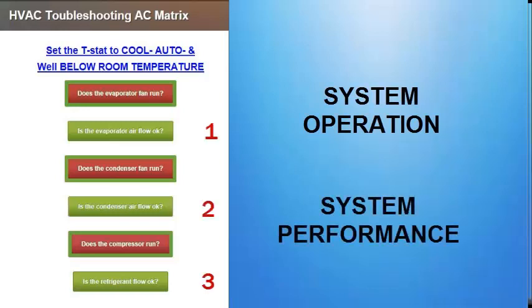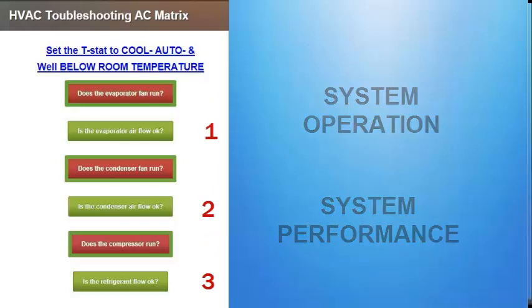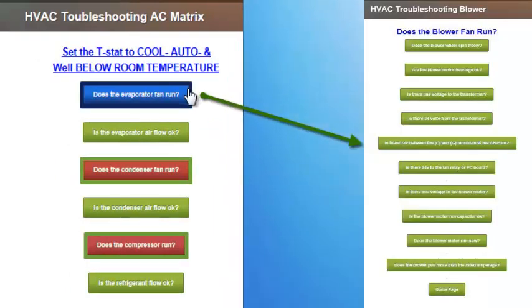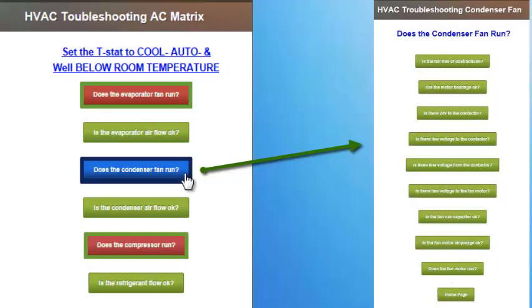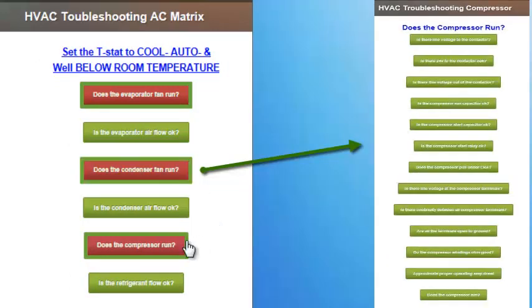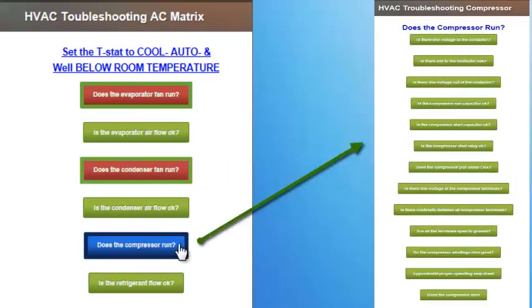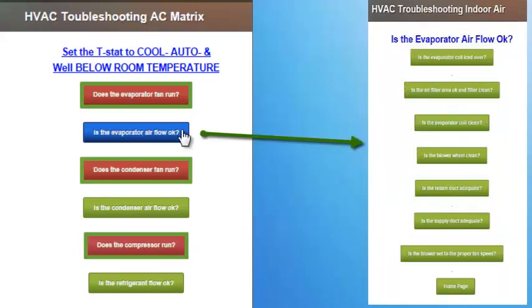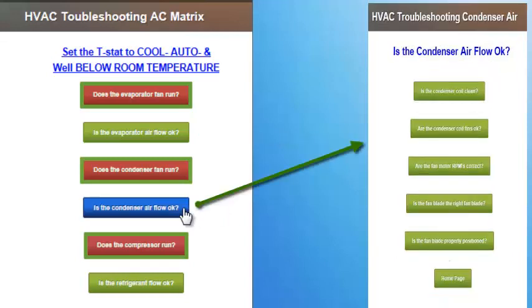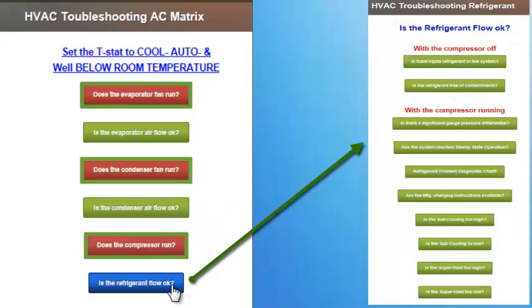When it comes to system operation, the technician wants to know: does the evaporator fan run, does the condenser fan run, and does the compressor run? When it comes to system performance, the technician wants to know: is the evaporator airflow okay, is the condenser airflow okay, and is the refrigerant flow okay?